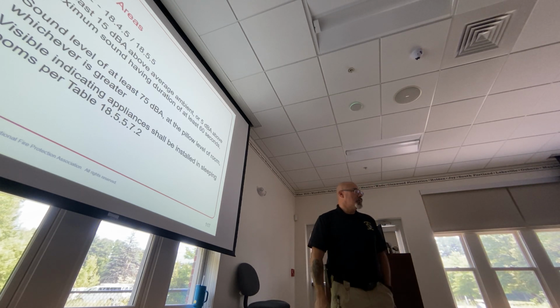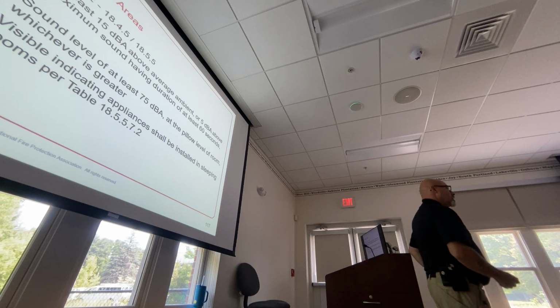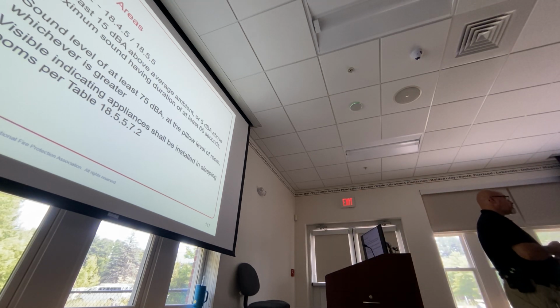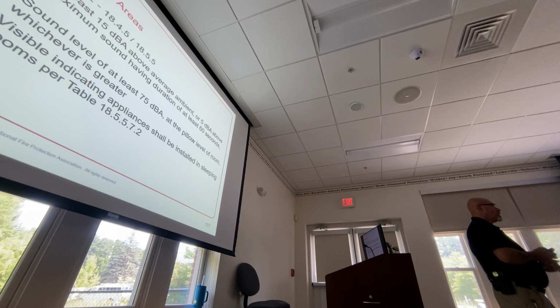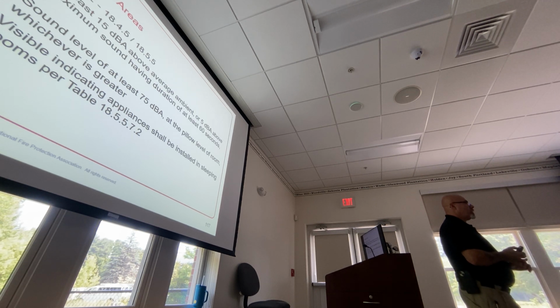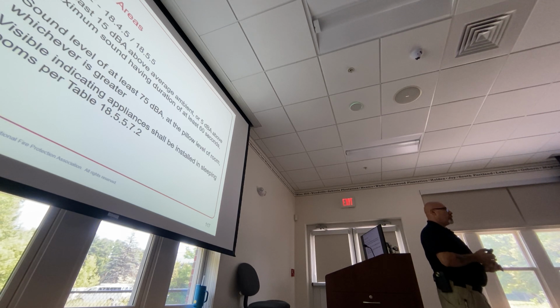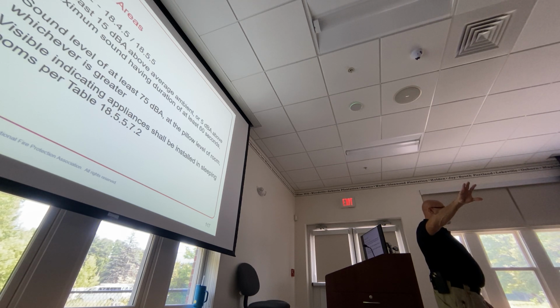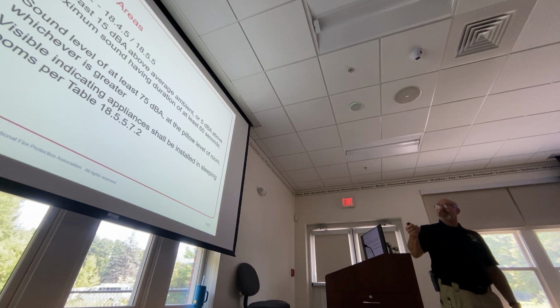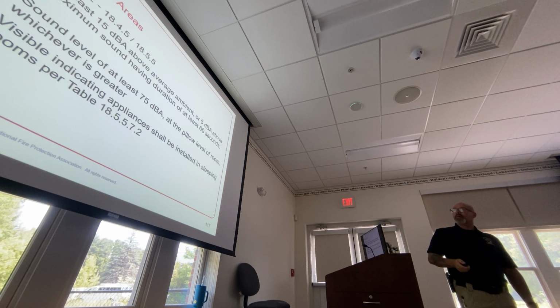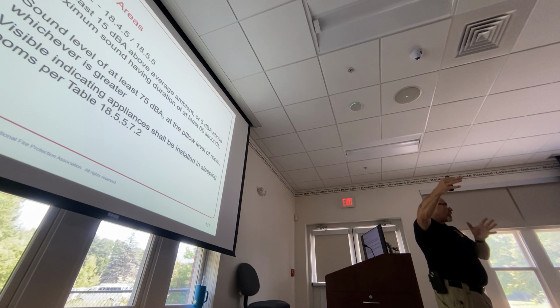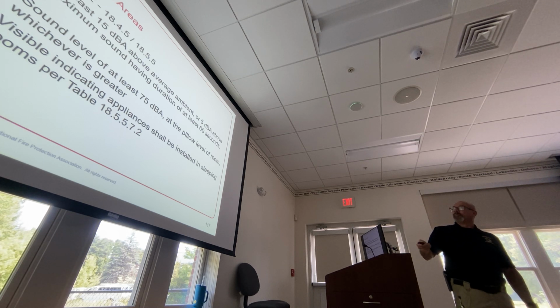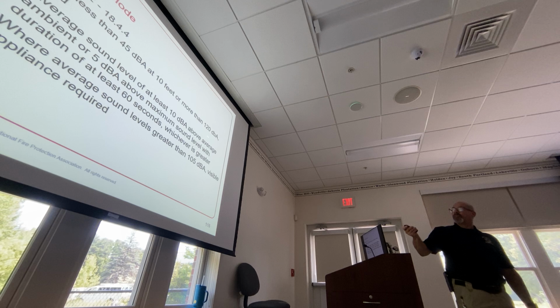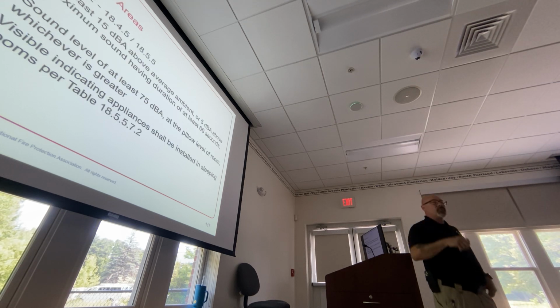Are those allowed to be gradient? Like, you know how notifications in fire stations start off quietly and then they grow? Typically, they're not that way. There's nothing that says that they can't do that, providing they're meeting the requirements when it first goes off. So it has to start at a certain minimum to notify you, a minimum of that 15 dBA above the normal sound, and then it can grade up from that as long as it doesn't go above 120 decibels. So it can be gradient at that point.